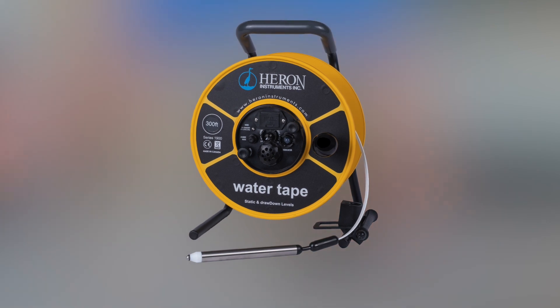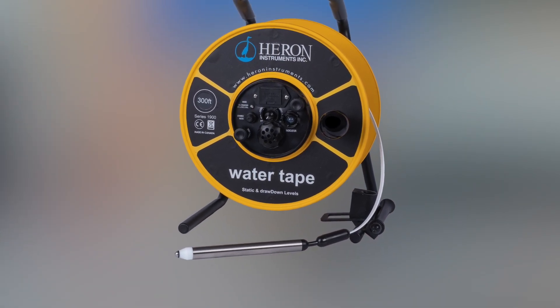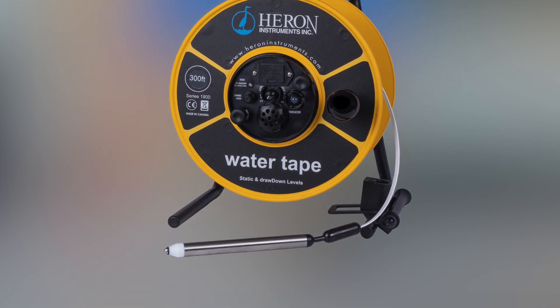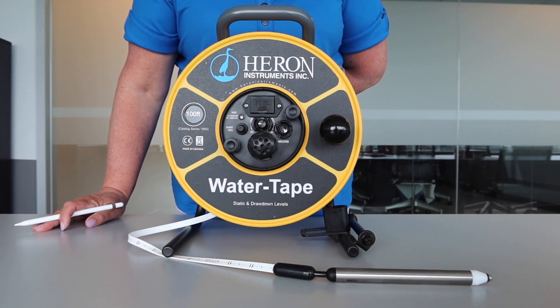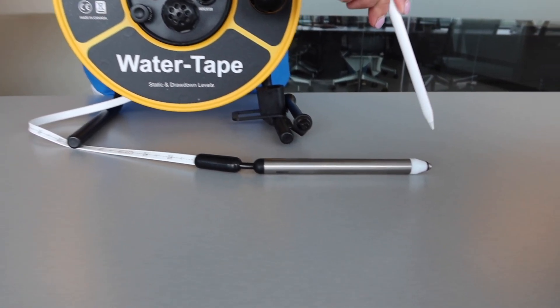The water tape comes with a fully submersible, permanently affixed, modular water level probe. This probe is used to detect both static and drawdown levels. When you lower the probe into the well, the unit will start to sound immediately when it comes into contact with water.